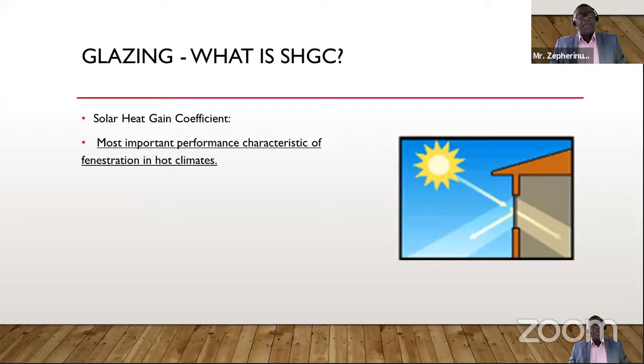A little bit more about the glazing. What is the solar heat gain coefficient, or the SHGC? The solar heat gain coefficient is the most important performance characteristic of fenestration in hot climates like us in the Caribbean region. And the image on the right clearly explains that. So we are seeking to have a high performance window or fenestration that would reduce the amount of radiant heat coming into the building from the sun.